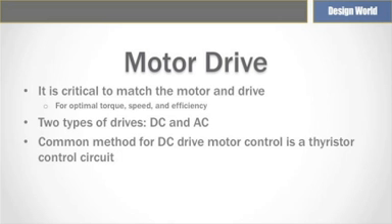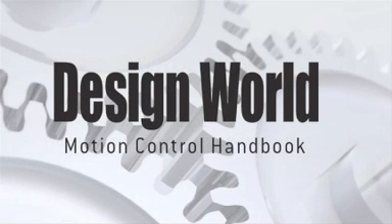DC drives control DC motors. A basic DC drive is similar in operation to an AC drive in that the drive controls the speed of the motor. For DC motor control, a common method is a thyristor-based control circuit. These circuits consist of a thyristor bridge circuit that rectifies AC into DC for the motor armature, and varying the voltage of the armature controls the motor speed.